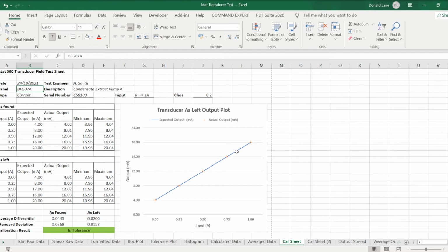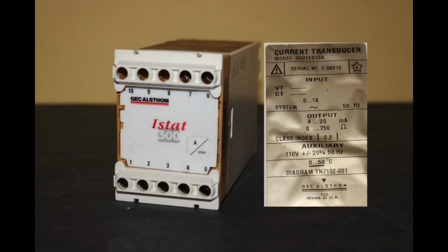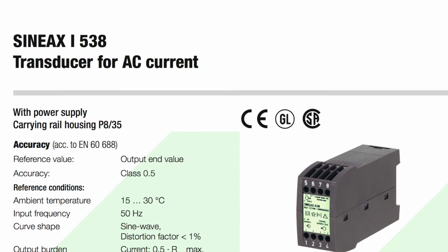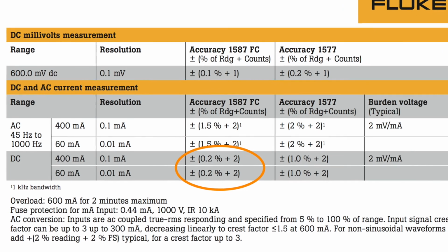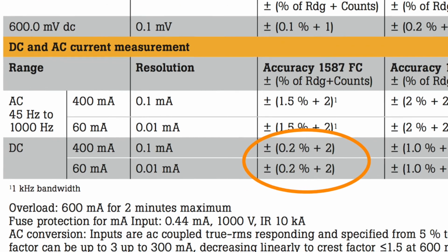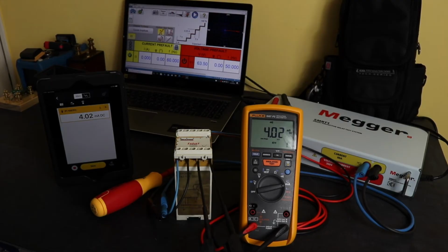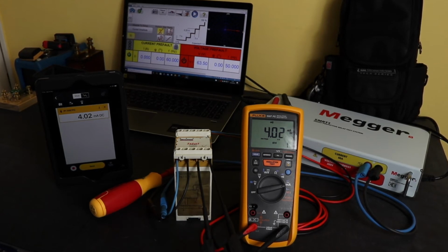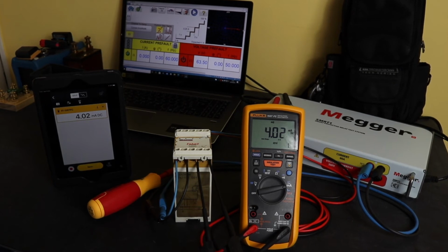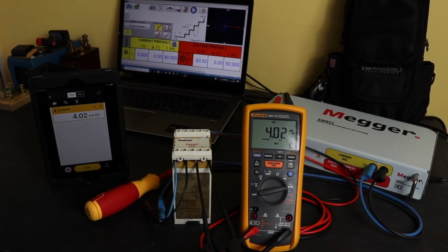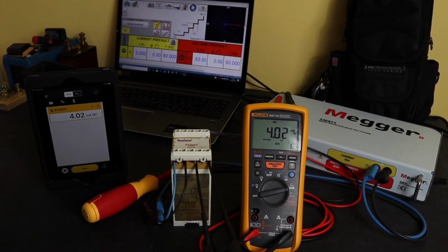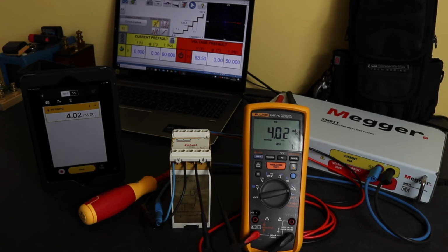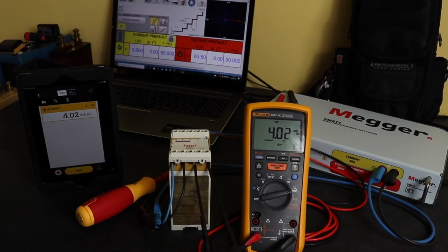So that leads on to another issue that I just need to make you aware of with this setup I've got, and that is the actual tolerances that I'm working to. You can actually see, as I said here, the class is 0.2%. For this particular transducer, for a Sineax transducer, it's actually 0.5. The Fluke has a tolerance of 0.2% on the current milliamp scale that I'm using to take these measurements. So for this transducer, you can just about get away with it. Ideally, you want a minimum of 3 times better tolerance for the instruments that you're using to take the measurements. So that would be reasonably close for the Sineax transducer. For the Istat transducer there, it's not. It actually equals the class.